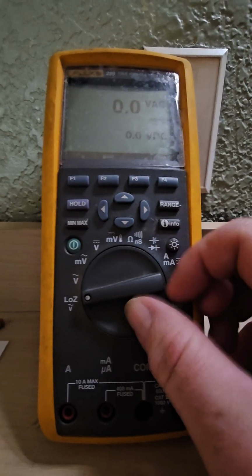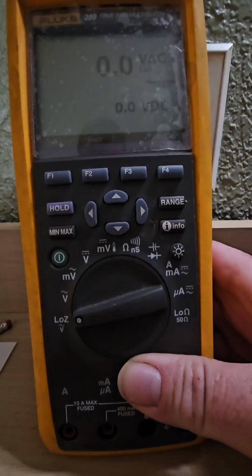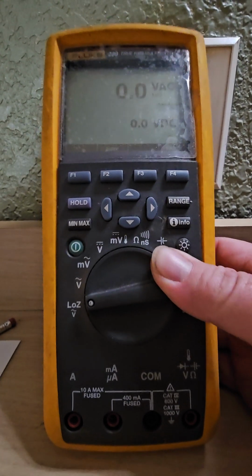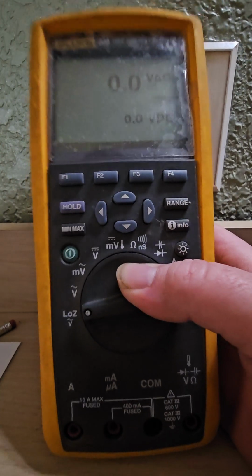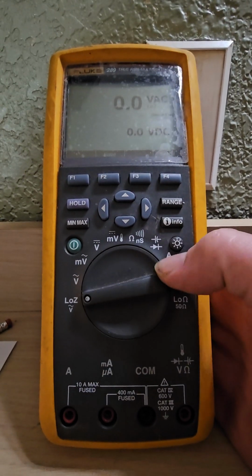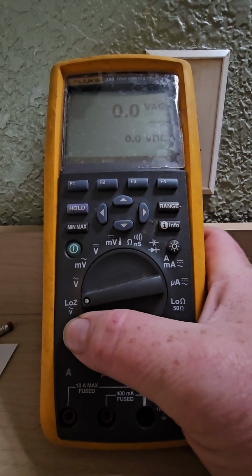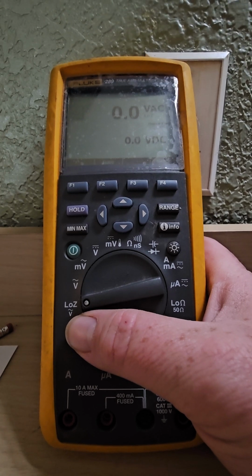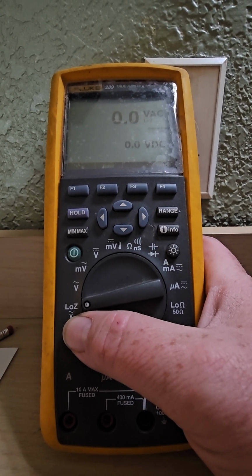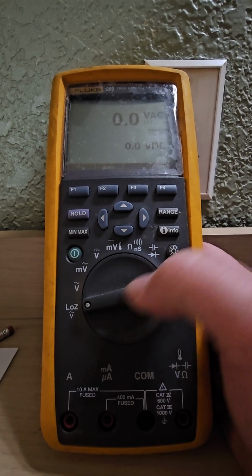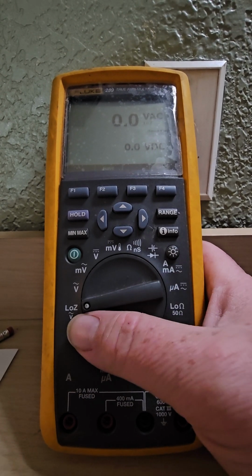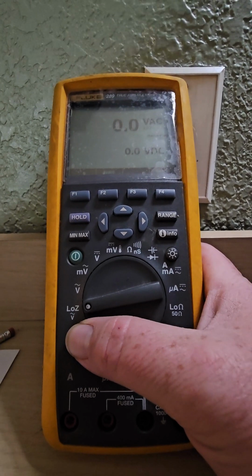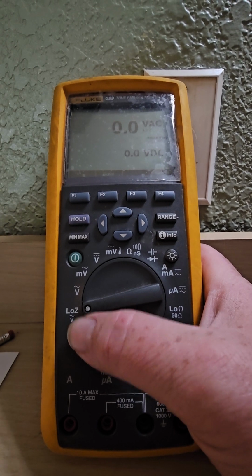Here's a brief introduction of some of the functions of a digital multimeter or DMM or whatever they want to call them nowadays. Most people just call them their meter because we don't use analog anymore. I haven't seen analog in a long time. But this low Z function, that's for eliminating ghost voltages. You use that for more troubleshooting in an AC circuit because it uses an impedance. It'll get rid of stray voltages in a circuit. You'll find loose connections. It's not as handy as I thought it would be, but it does help sometimes.